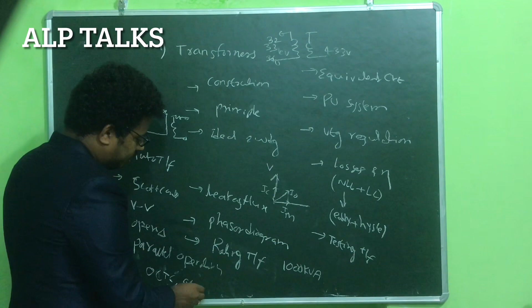And every time it is not true that whatever voltage we are applying to the primary side, it may not be fixed, right? It can be 32 or it can be 34 kV instead of 33. In those cases, generally we don't get proper 433 volts. So we need tap changers mainly. We need off circuit tap changer. If it is an important application, we need on load tap changer. For example, some areas we can't shut down the supply, so we need on load tap changer. These things we are going to discuss.